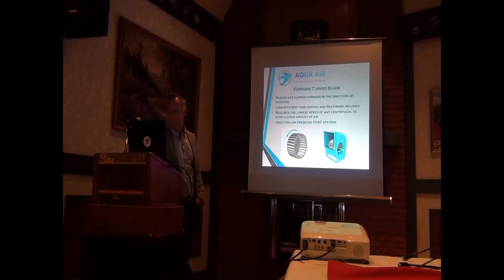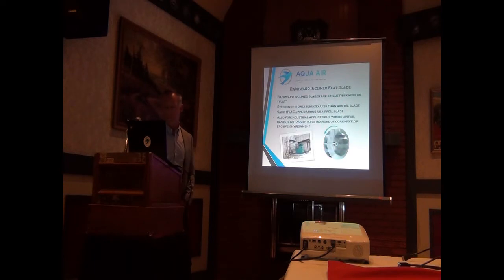And like I said earlier, these will be mounted on a base with a pulley and drive system. They're not the most efficient fans. We'll talk about fan curves. But whenever you have a motor and a belt drive system, there are additional losses to the overall system with that.